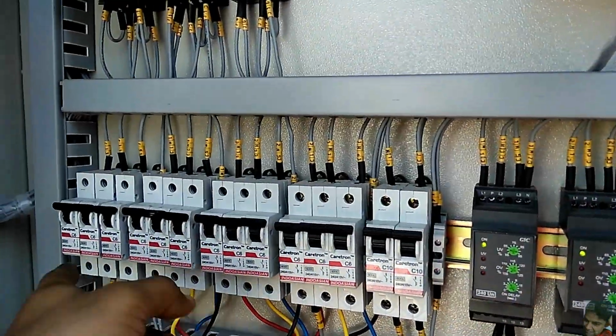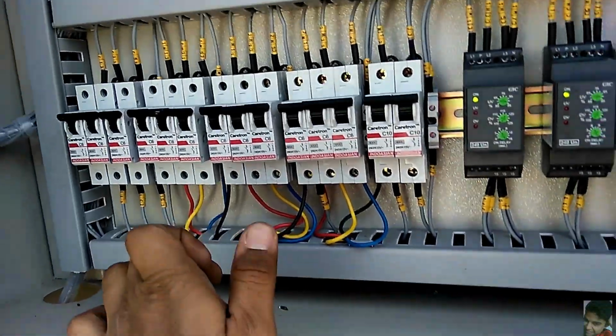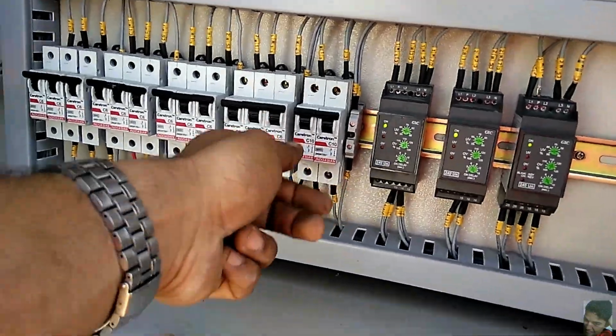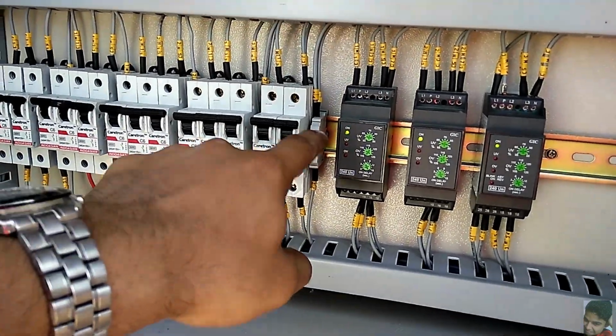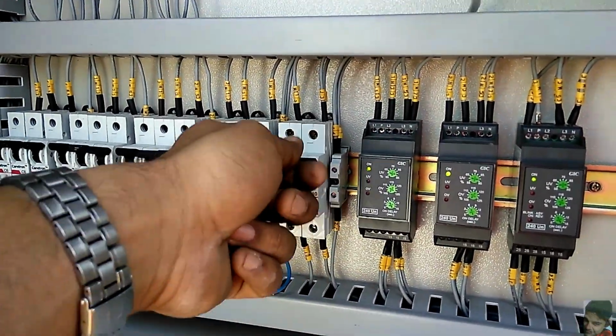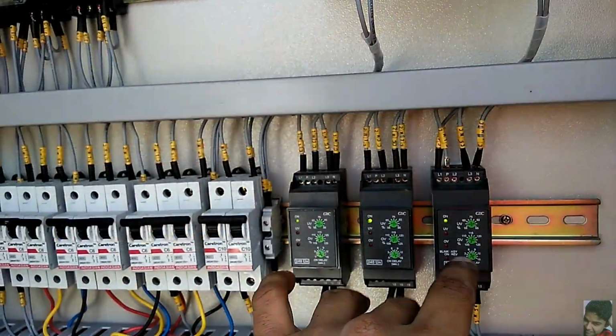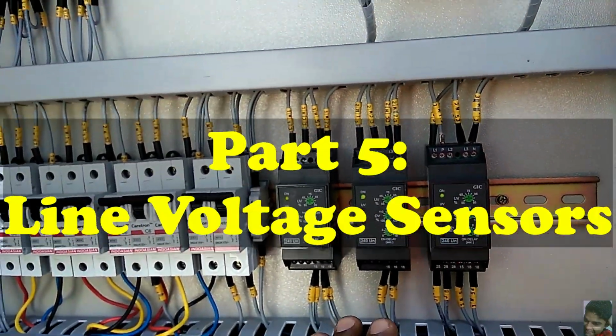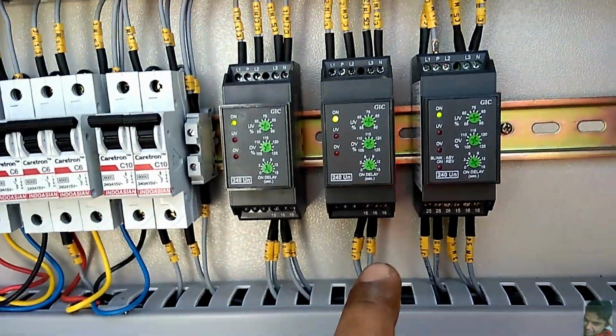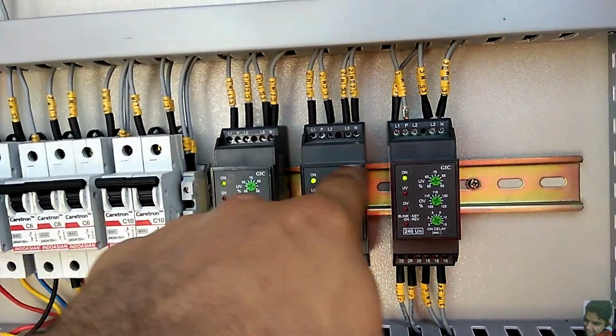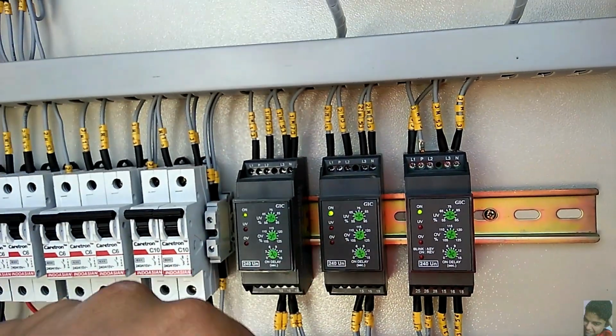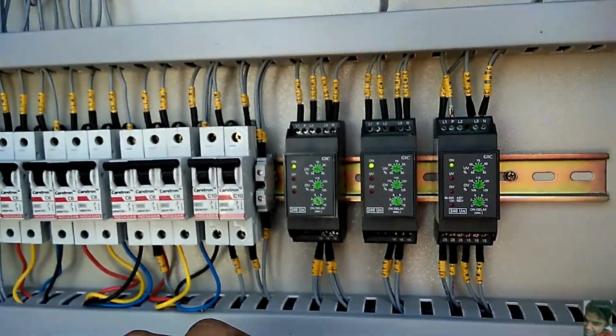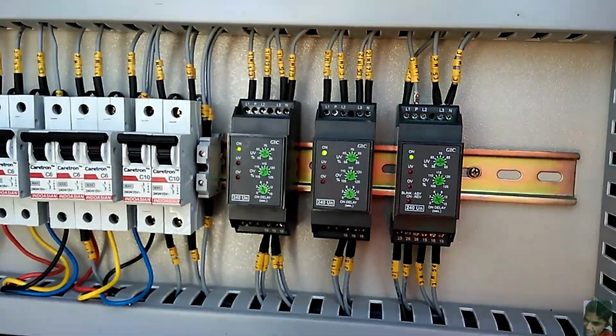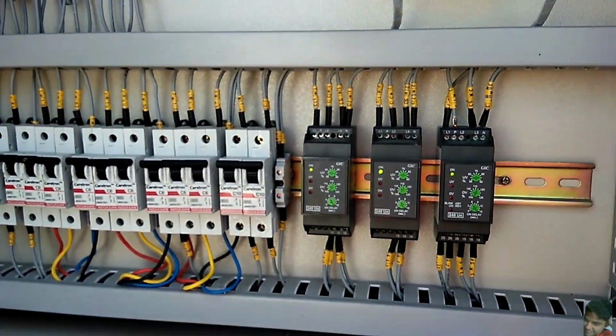It could also be that one of these breakers is tripping for whatever reason, and you can do the same thing again. So right now it's all on. If it's tripping, it will be in some center position, so you have to off it and then on it. These are the line voltage sensors. This is what tells the generator to start. So when this is on, it means the electricity is there from the mains, and when these go off, it will be like, okay, generator, there's no main power, so you must start now. That is what it means.